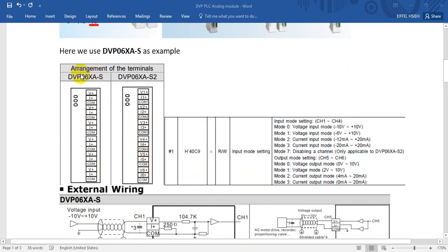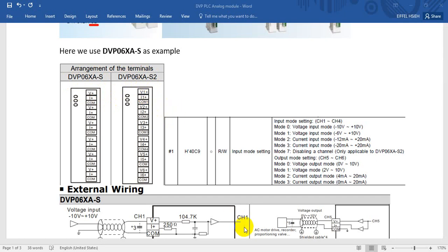You may wonder what the difference is between these two modules. Basically it is two points: first is the input impedance, and the other is the circuit design — one is with isolation and one without. You can find more detail in the installation user manual. For the 06XA module, we have four inputs and two outputs. As you can see, we have a total of six channels — four channels for input and two channels, channel 5 and channel 6, for output.